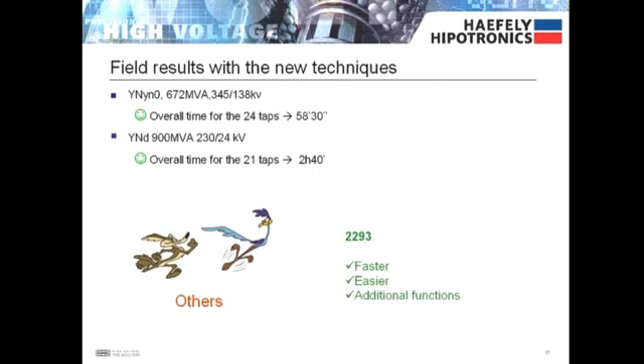For example, the 2293 is able to measure a wye-neutral wye-neutral 672 MVA transformer with 24 taps in just under one hour, and a wye-neutral delta 900 MVA transformer with 21 taps in just two hours and forty minutes.